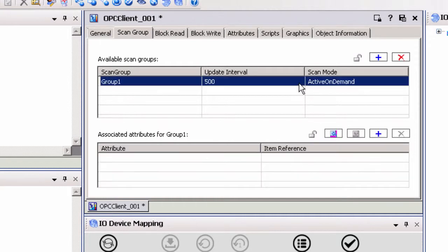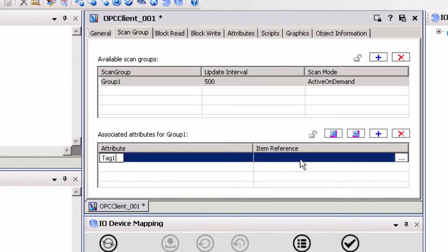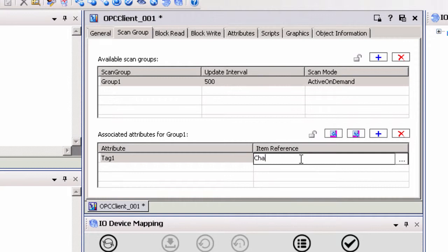First, we will add an item by manually configuring the item reference. We will enter the item address in the item reference column in the form channel name dot device name dot item name, where the item name can either be an actual tag name configured in TopServer or a PLC address passed down in the item name. If using a device address, the format should be device address at data type, where the at data type is an optional appendage. If not specified, the default data type for the device address will be used. For our example, we will use channel1.device1.tag1. If we were using a dynamic address, we would enter channel1.device1.r0001@word, where r0001 designates the address in the PLC and @word specifies the desired data type.